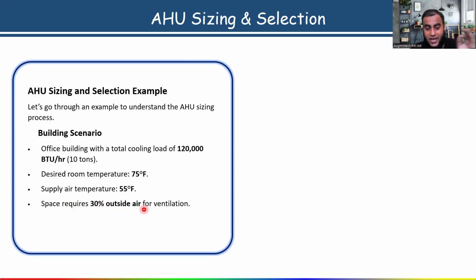Here we have done the assumption. I have assumed 30% outside air for ventilation. But remember to calculate the fresh air, and the total building area is 10,000 square feet. How will you calculate the fresh air requirement? How much fresh air? Suppose for which space you are designing, let's say any classroom.